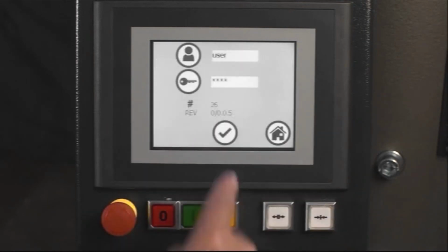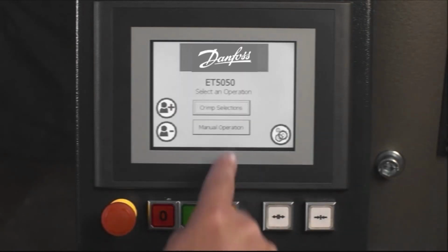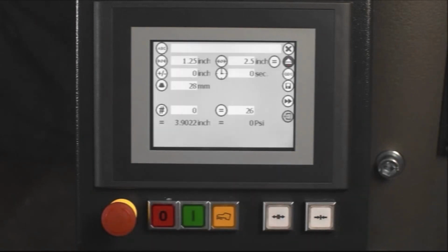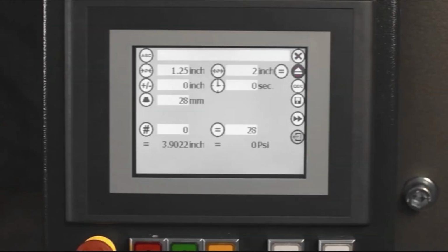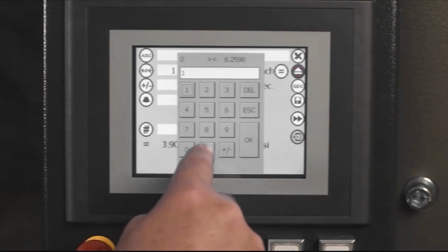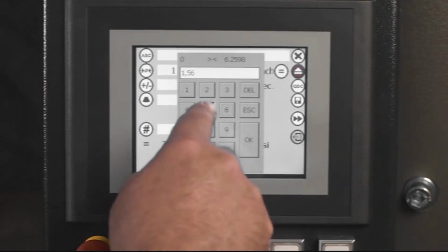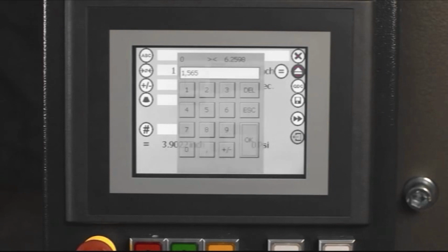After entering the username and password, press the check icon to enter. Now select Manual Operation for manual operation. In manual operation, the user must input the crimp specifications and may save to a user-specified name. Procure the appropriate crimp specifications, tolerances, and build information from the appropriate source.